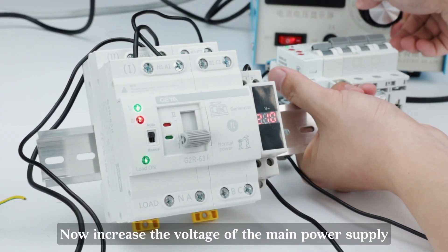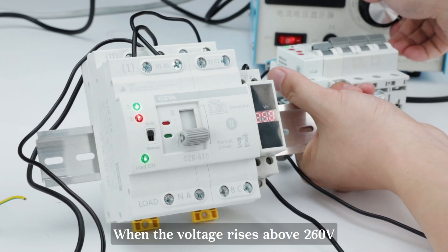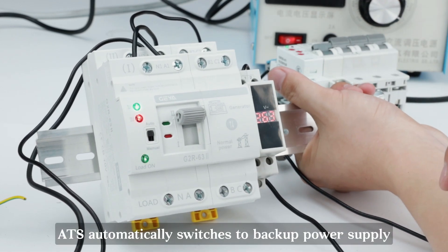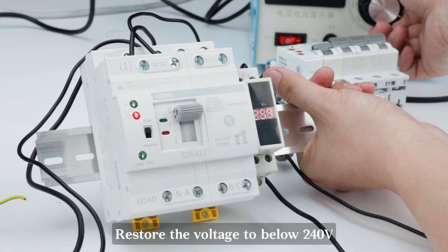Now increase the voltage of the main power supply. When the voltage rises above 260V, ATS automatically switches to backup power supply. Restore the voltage to below 240V.